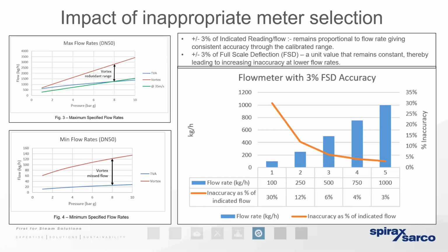So first of all, let's look at full-scale deflection. If a flow meter can pass 1,000 kilograms per hour of steam at 100% capacity, a full load, and it's been quoted as having a 3% full-scale deflection accuracy, that means there could be 30 kilograms of steam that is not being read by the meter. But then if the process falls to a low load, say 100 kilograms per hour, the meter is still failing to measure that 30 kilograms per hour. So what was a 3% inaccuracy at full load becomes a 30% inaccuracy at a lower load. It's therefore far better to have an understanding of what we call an indicated flow accuracy. That basically means the percentage accuracy or certainty is going to remain the same regardless of the flow rate we're looking at.